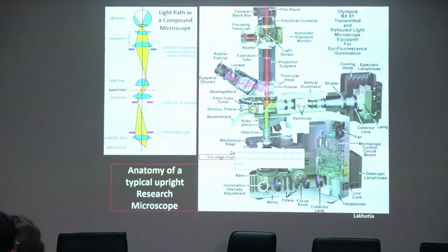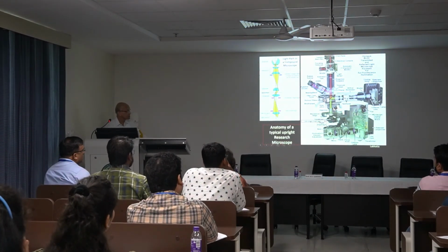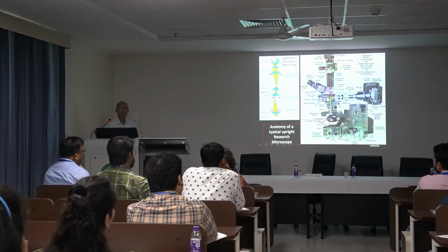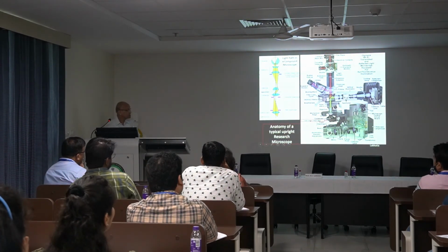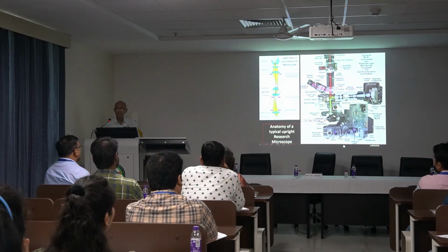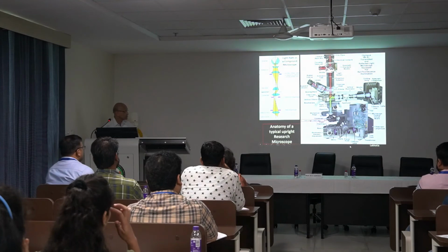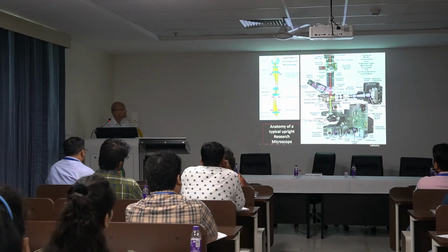Now this is how a typical standard microscope works, with the light source here, light gets reflected up, down the condenser, and this is an important function. And I think to get the best of the microscope, we must learn how to adjust the proper illumination. We can get a light, all right, but then we can't get good resolution unless the light is properly centered, the diaphragm size is properly controlled, and so on. And that's what this condenser does, that function in an upright microscope.